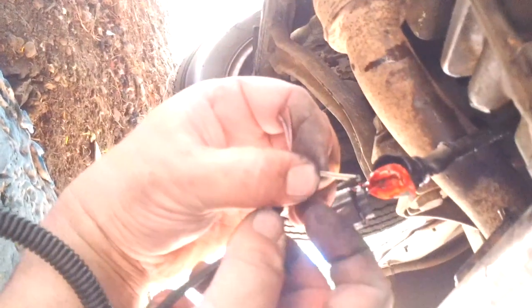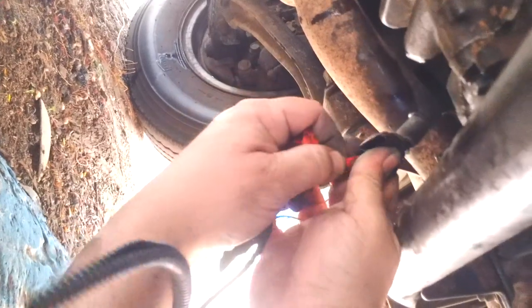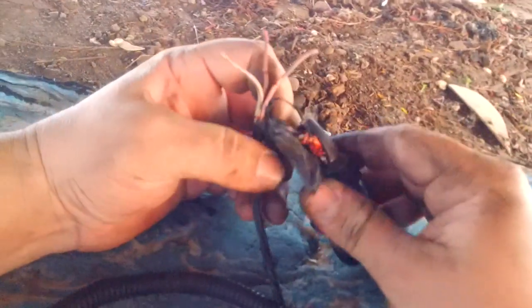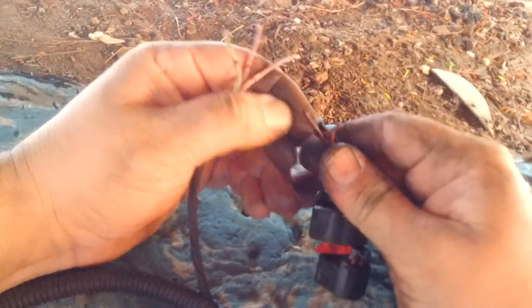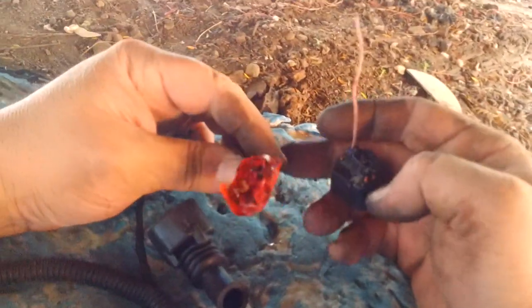We need to find out what our wiring is: pink, pink and black, pink and blue, and white and black. Looking at it from this side — two down, three down. Comparing both sides. If not sure we can get a meter across it. So we'll get rid of the excess and that basically just leaves us with one — the pink.